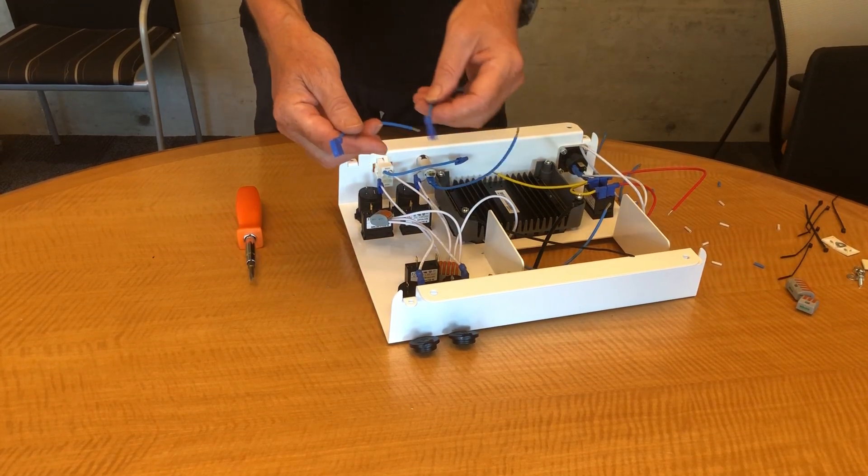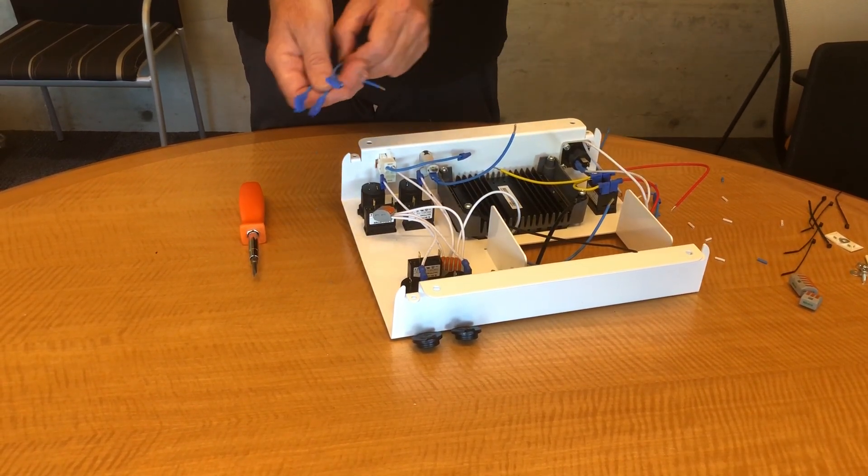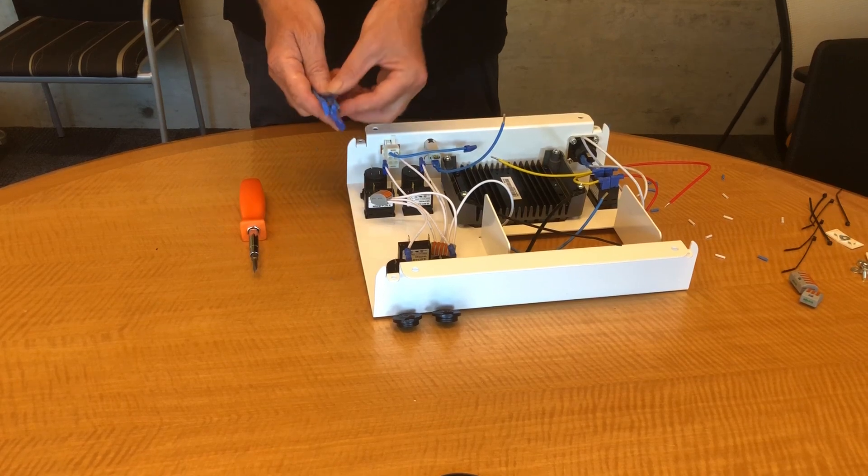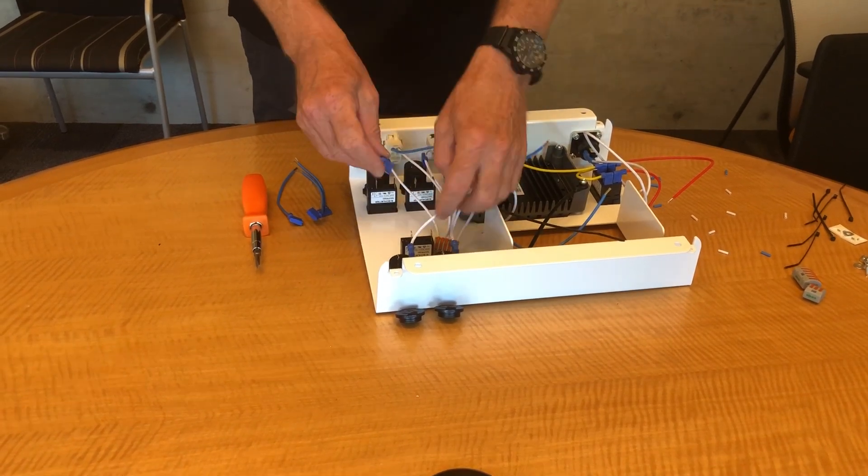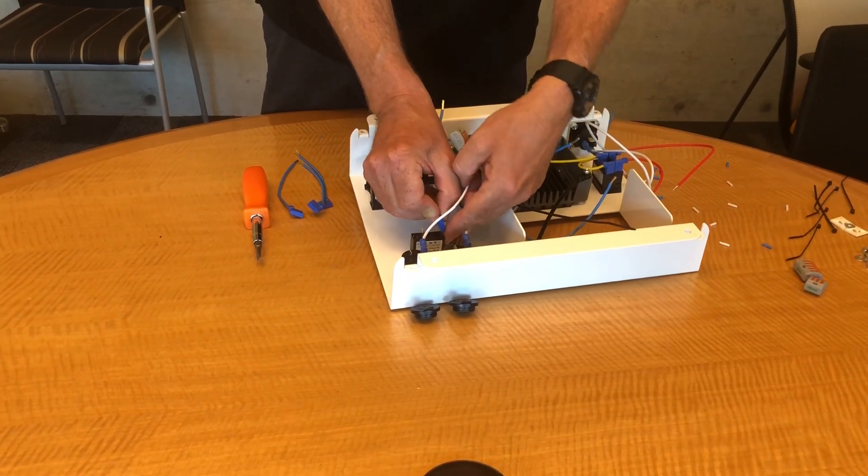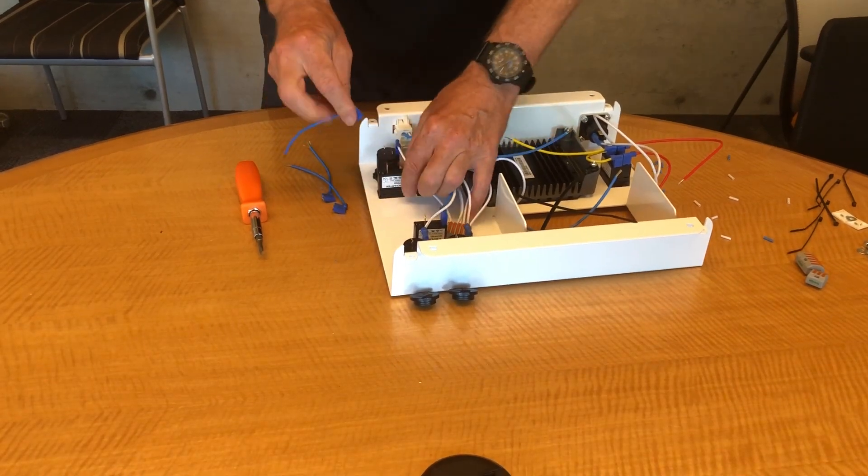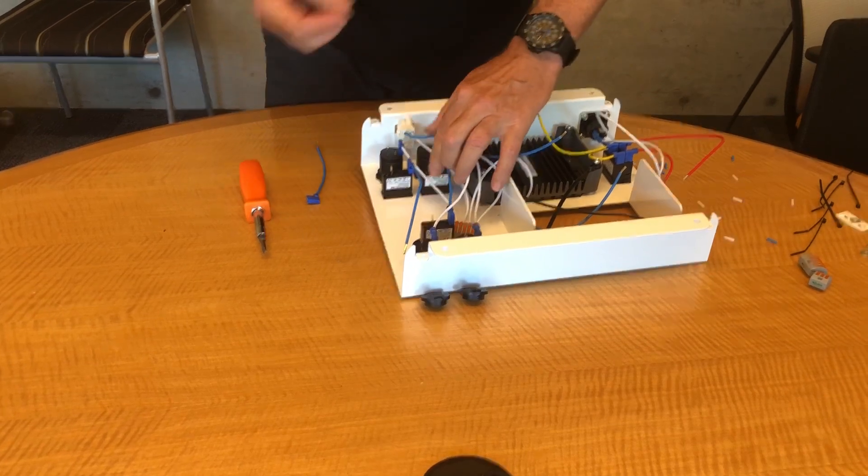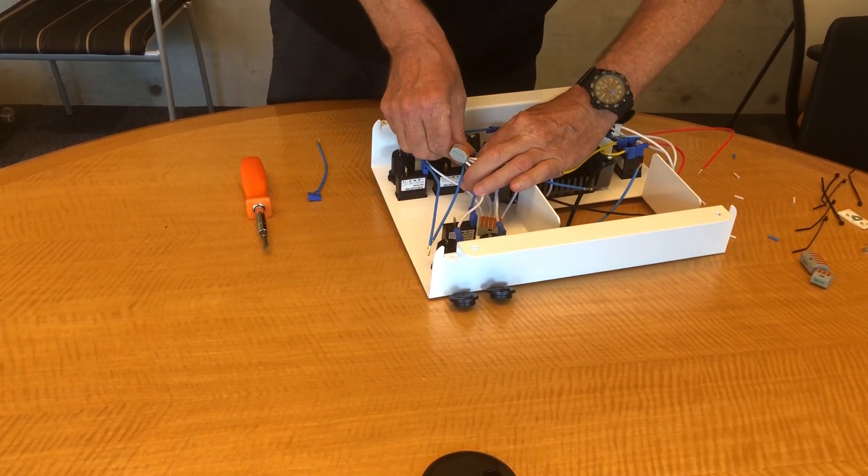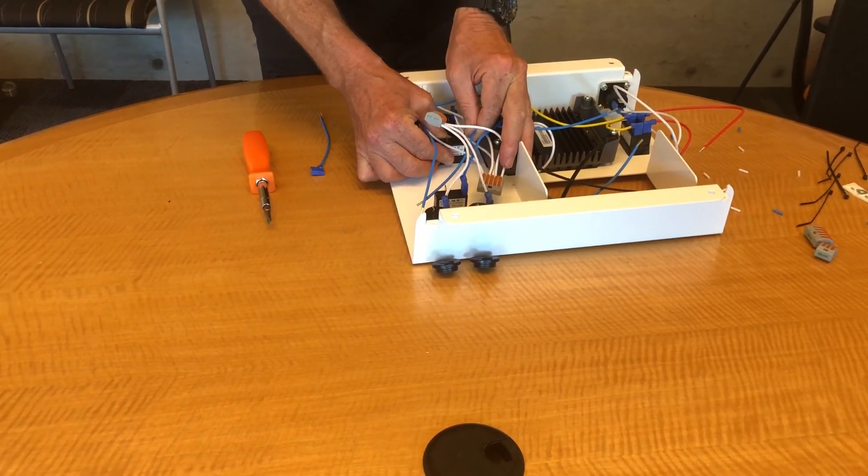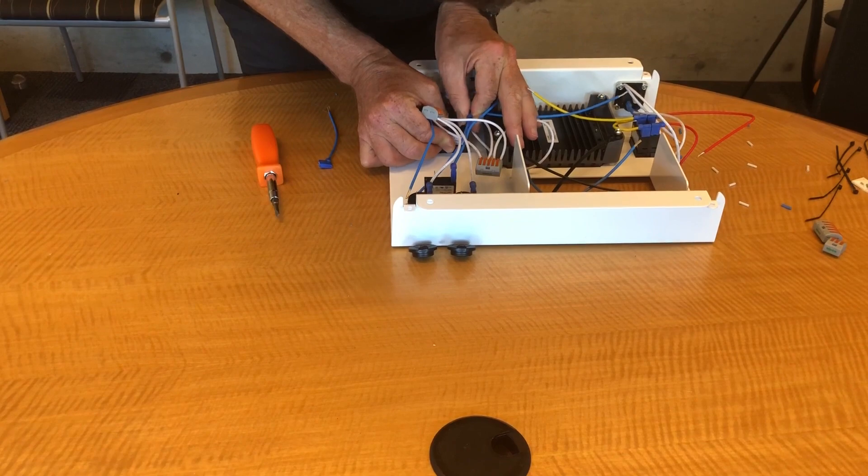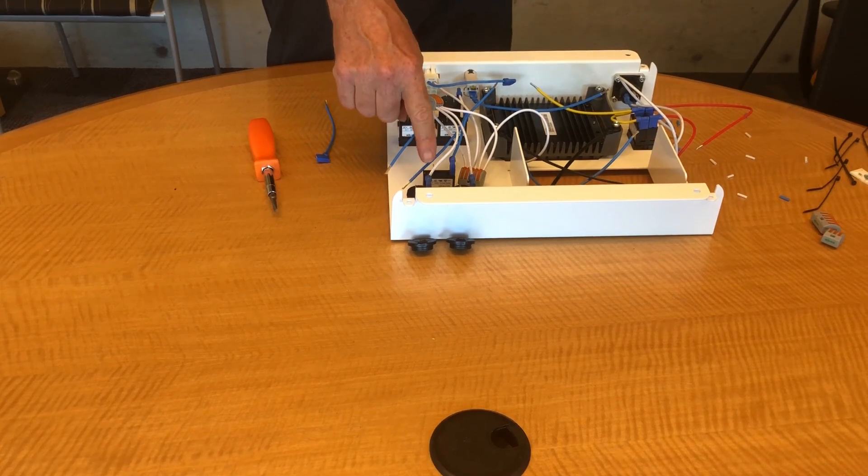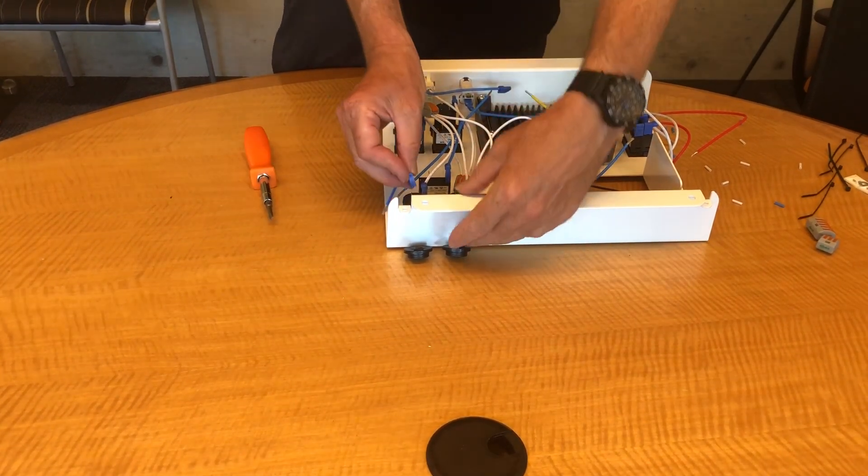So this one is going to power or energize the expansion port. So I'll put this one on this breaker. So then these blue wires with the flags are going to feed the circuit breakers, which will then feed the sockets. So you put these on to this end of each of the breakers. And you can support the breakers you put it on, and that's a good idea to protect it. So we've got these three, and then it's going to go from this breaker and feed these two. So I'm going to go ahead and put these on also.